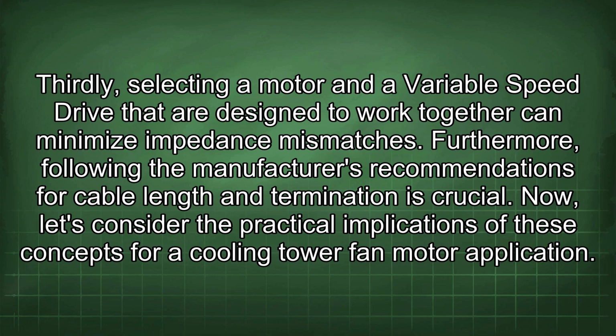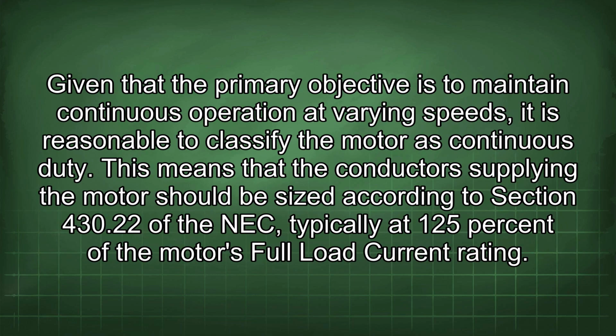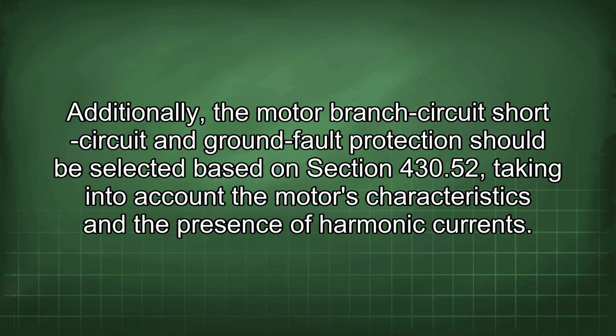Now, let's consider the practical implications of these concepts for a cooling tower fan motor application. Given that the primary objective is to maintain continuous operation at varying speeds, it is reasonable to classify the motor as continuous duty. This means that the conductors supplying the motor should be sized according to Section 430.22 of the NEC, typically at 125% of the motor's full load current rating. Additionally, the motor branch circuit, short circuit, and ground fault protection should be selected based on Section 430.52, taking into account the motor's characteristics and the presence of harmonic currents.